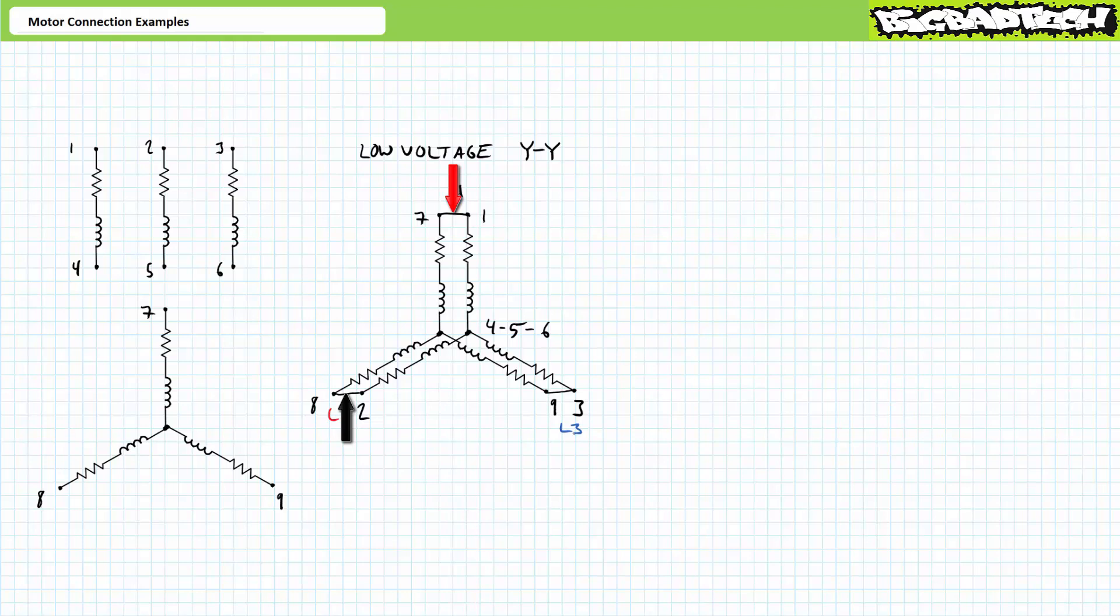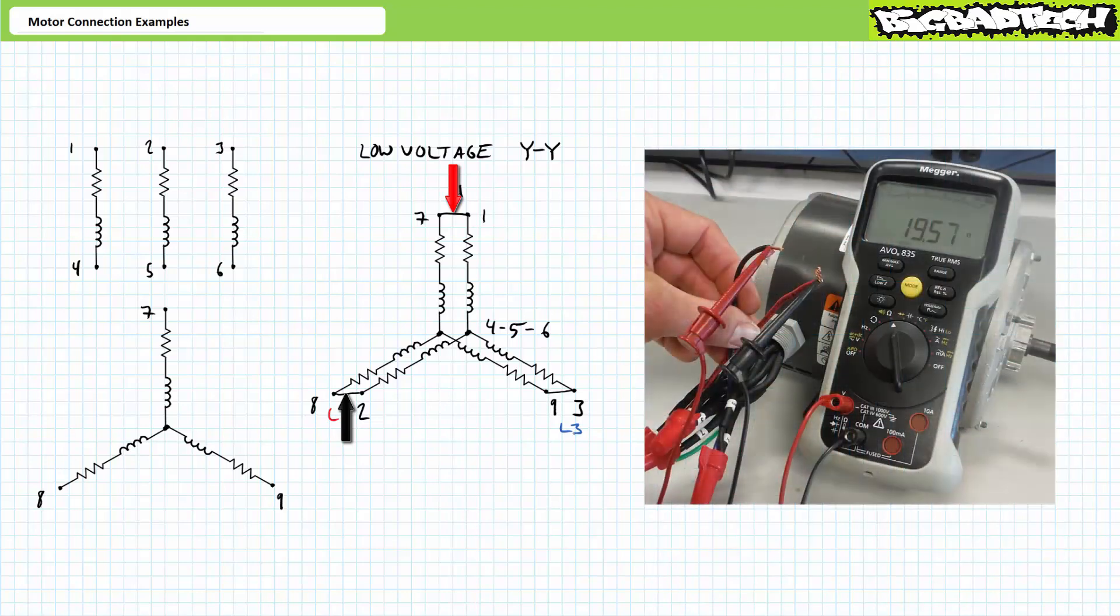If each of these windings is 20 ohms, each series path is a 40 ohm path. Two 40 ohm paths in parallel is 20 ohms. An ohmmeter between conjoined terminal one-seven and two-eight does indeed see a resistance of roughly 20 ohms as we might expect.